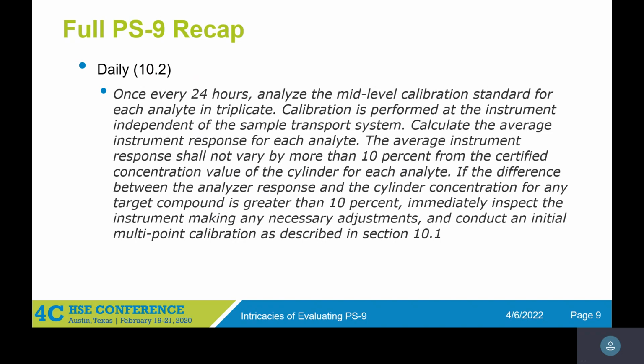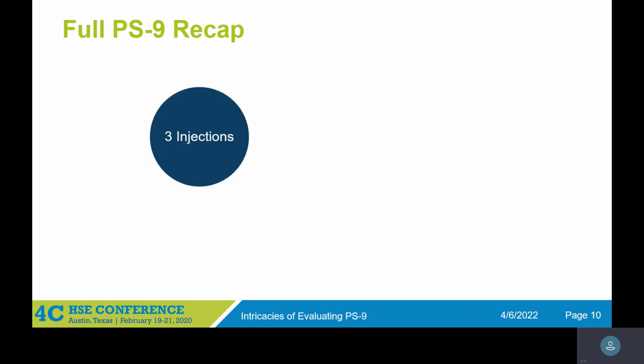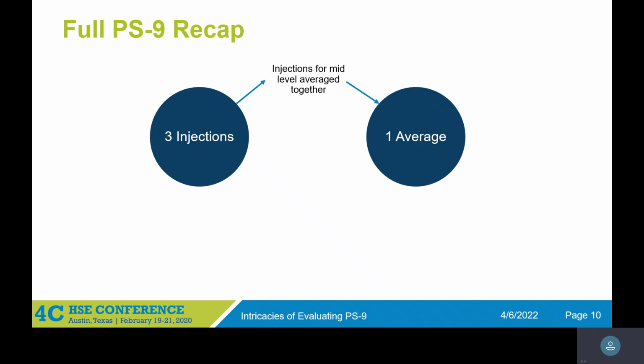Beyond the multi-point validation, which should be run anytime there's maintenance or initial certification, or at least once monthly based on PS9 as written, there's also the daily. The daily is at least once every 24 hours, and this one's a little easier. It's just the mid-level in triplicate. So there we would have just 3 injections instead of 9. Those are averaged together, so we'll end up with one average from those 3 injections, and then we just have to make sure that average is within the cylinder concentration. So there's no going back and having to verify each individual injection within a percentage of that average.